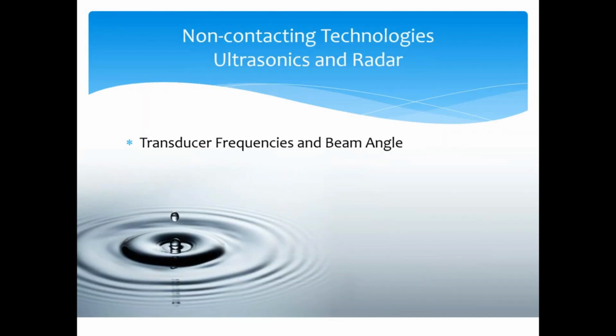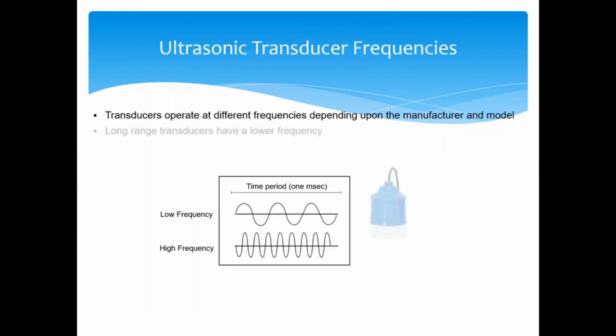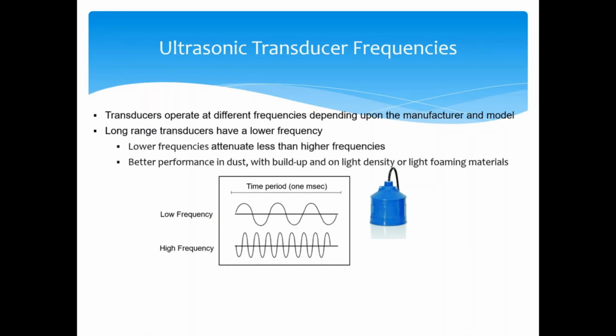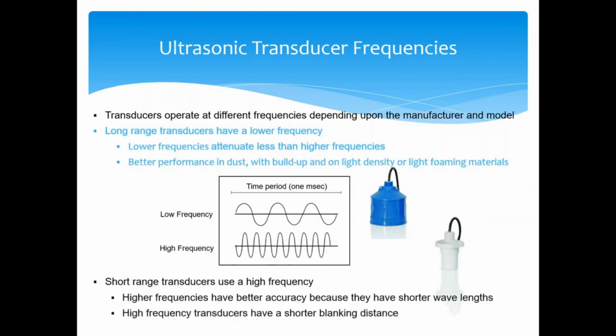Okay. So now we're going to talk a little bit about different frequencies and how that relates to different beam angles and where that might be important to you. All transducers are going to operate at different frequencies, whether that's radar or ultrasonic. Your longer range transducers are going to have a lower frequency. The key to take away from that is lower frequencies have less attenuation, so they're going to perform better in more challenging applications. Things like dusty environments, build up on your transducer or your horn, or dealing with some lighter foaming materials. Short range transducers use a higher frequency, and they're advantageous because you have better accuracy due to the shorter wavelengths, and you might have a shorter blanking distance, or in some cases, no blanking distance whatsoever.